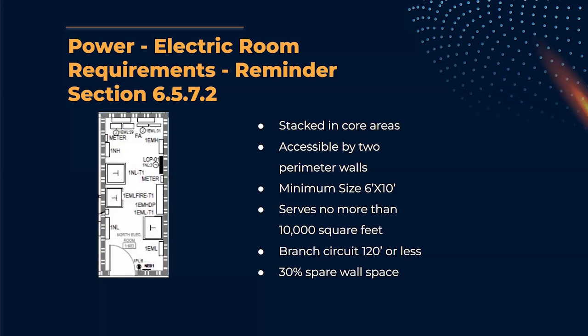There could be multiple tenants on a floor. We want to stay close to our electric room and distribute accordingly throughout those spaces. Branch circuits are limited to 120 feet or less. Again, that goes along with the voltage drop. We don't want to be upsizing conductors and things like that.